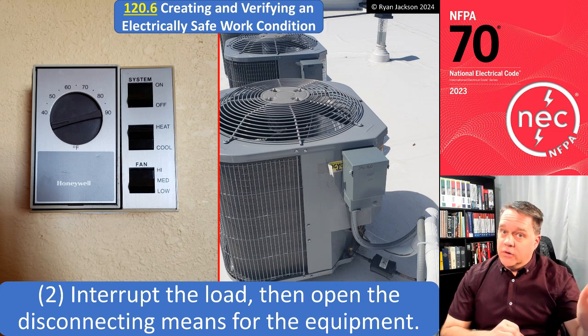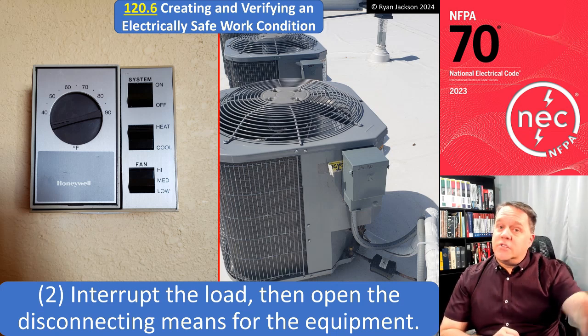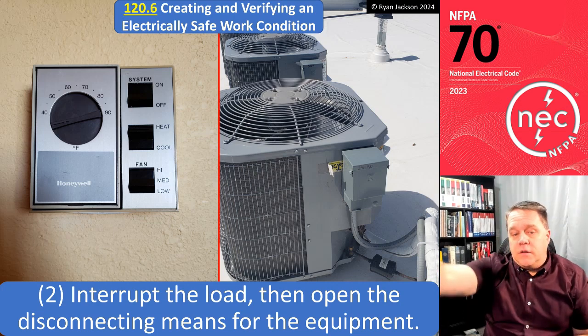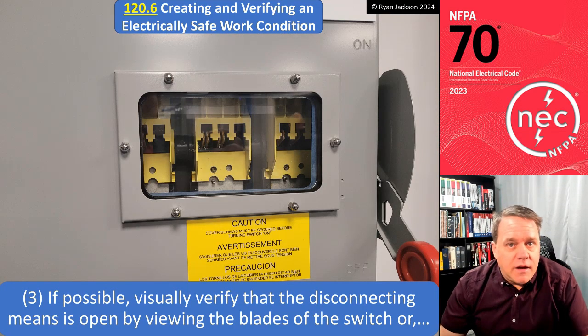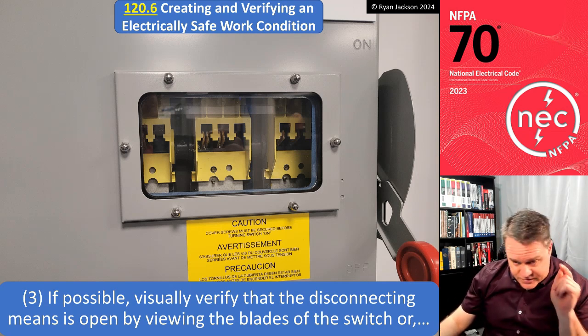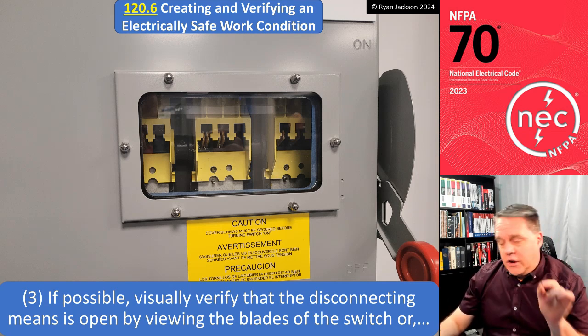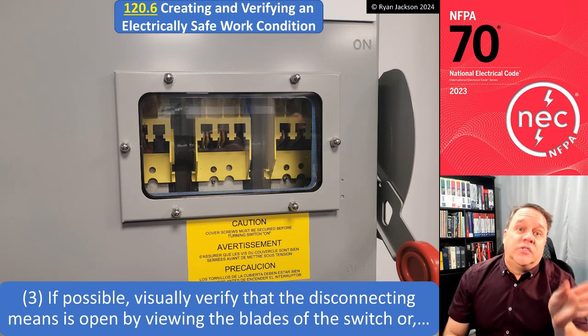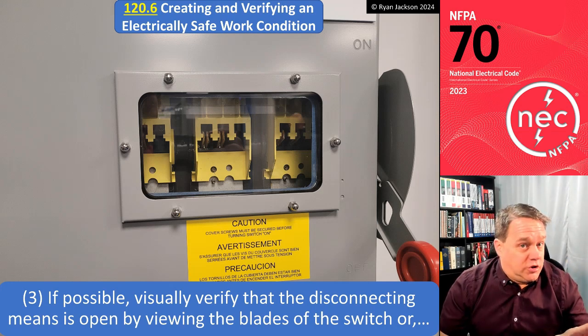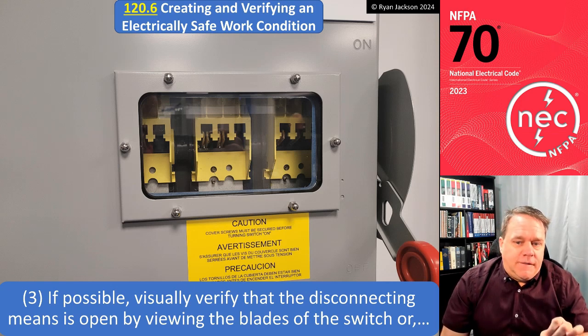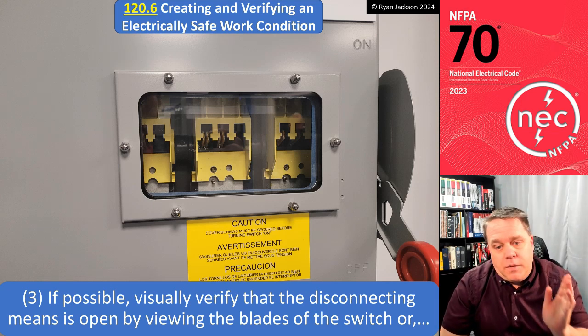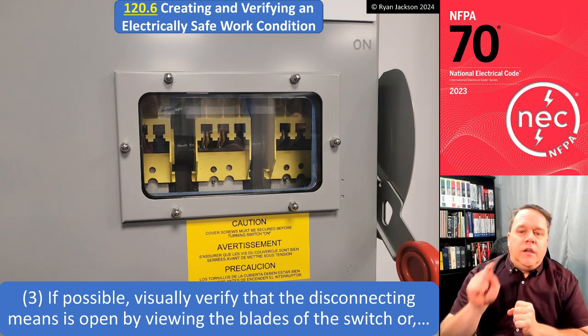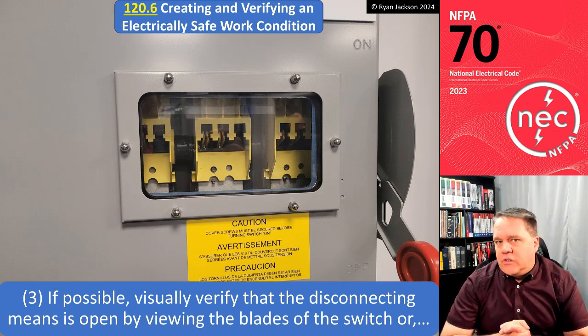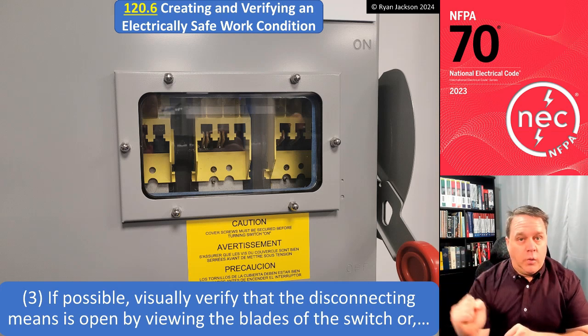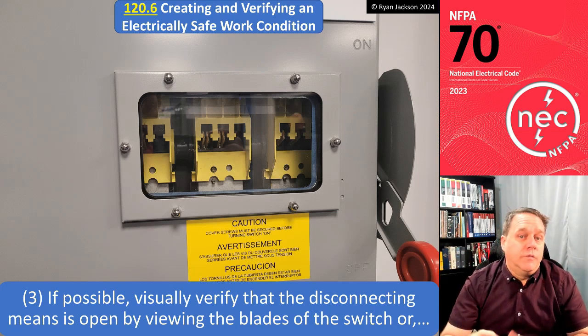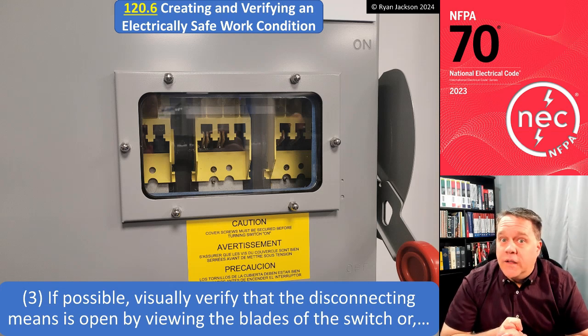That's not locking it out. That's not isolating it, right? That's just stopping the motor spinning. Then work the disconnect. Then item 3, if possible, and this needs to be changed badly in the standard, it should not say if possible. It should say if it's not going to create additional hazards, visually verify that the disconnecting means is open by viewing the blades of the switch. Here in this photograph, you can actually see the blades move when you work the disconnect. If we can see the blades move, well then yeah, let's watch the blades move. Why not? That's increased safety.